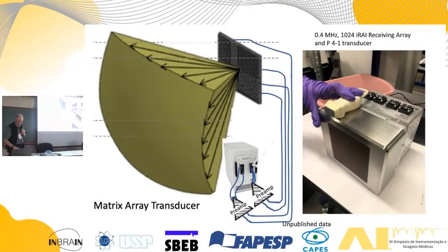Dose per pulse. We went ahead and designed a system that was designed for the radiation therapy units. So this is a 1024 element array. The elements are about 0.8 lambda on the side at 360 kilohertz. Turns out that's about 8 by 8 centimeters surface area. The whole thing with the preamps and everything weighs 35 pounds, and it's pretty big, so it gets in the way of a lot of your radiation therapy beams that you'd like to use. And you don't want to treat the transducer with the radiation therapy beam because the transducer can't handle that. You eventually damage the transducer elements. So we got this big array, and we're able to do some patients.